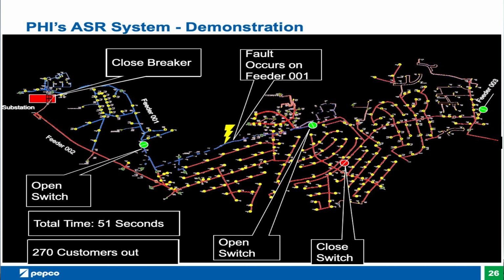An open switch would also allow us to deliver power from a different location. So basically we call that backfeeding to restore customers quicker. The service to the actual transformers. Service transformers, which we've seen in just different types. And then the closed switch. And basically this allows us to sectionalize the feeder. So if we have trouble in front of that sectionalizing switch, we can isolate, restore a portion of the feeder, and restore our customers even quicker.